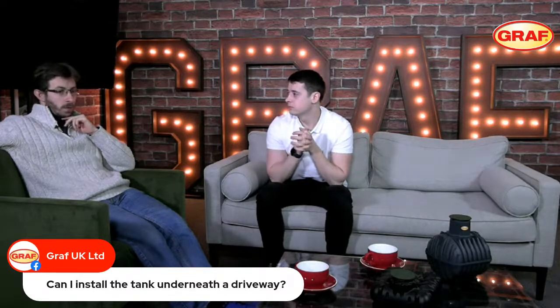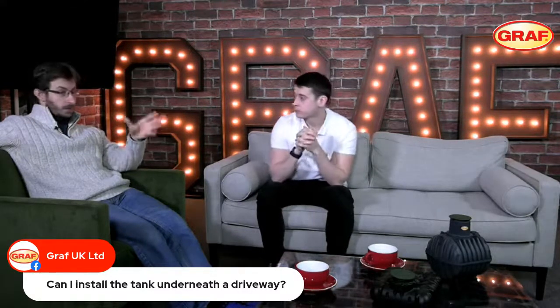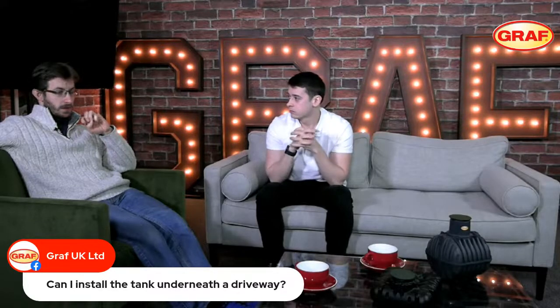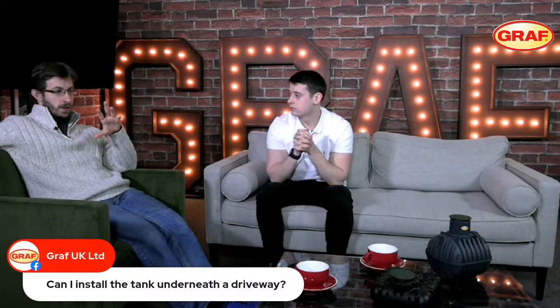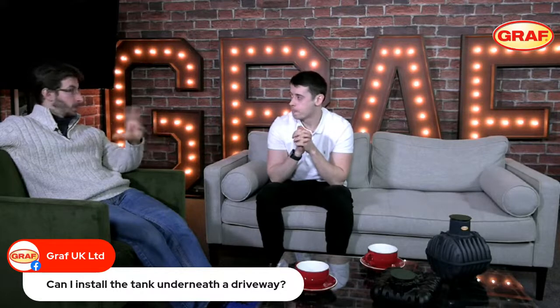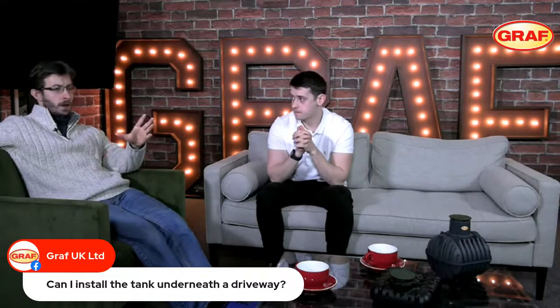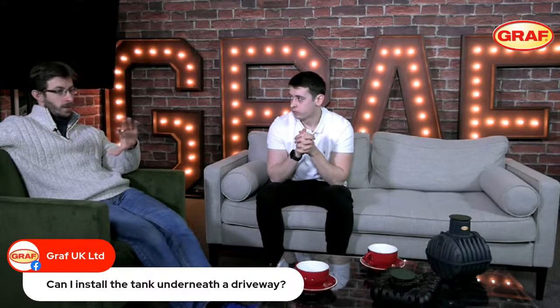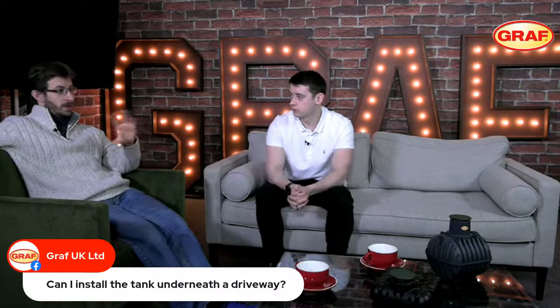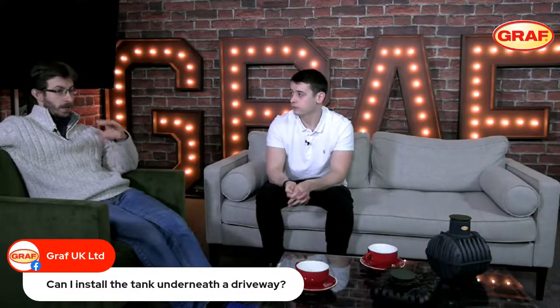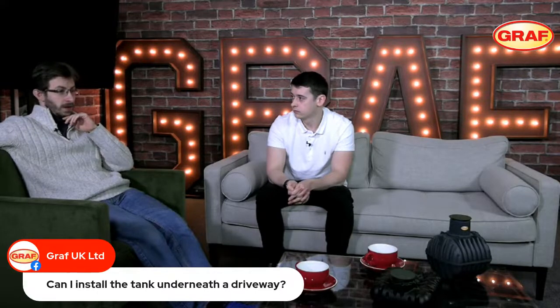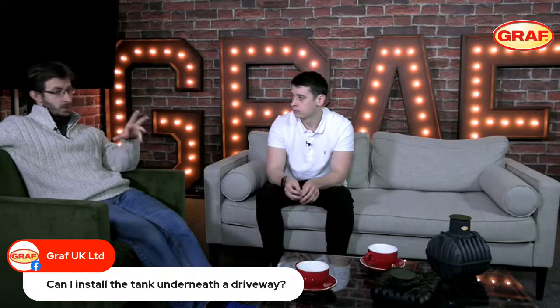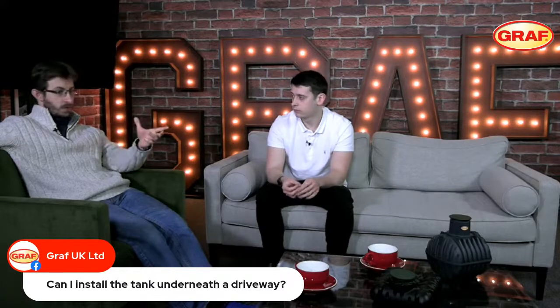Okay. With certainly Graf tanks, as well as many of the systems I'm sure you can find on the market, they are designed to support certainly light duty traffic loads. You may need to have a look at the cover levels over the tank to ensure you've got enough cover to distribute the load. And you also need to upgrade the tank cover. So with our systems, we'd normally supply a green pedestrian lid, which is quite flat, so it's discreet. We would upgrade that to a cast iron lid, which is suitable for light duty traffic.